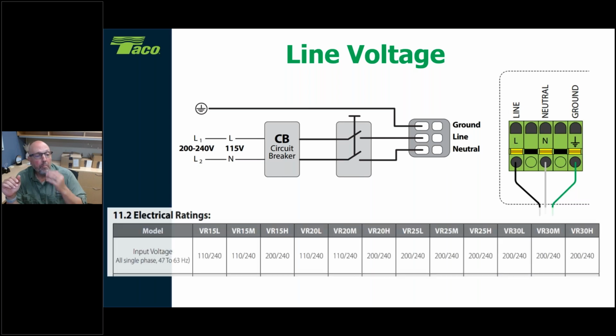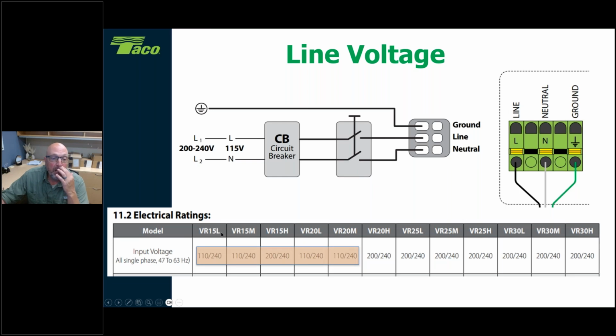Now, when we take a look at the models here, this is where I've seen some confusion, and a couple of phone calls have come in saying, hey man, my circulator's not running, it's really slow. I got VR15s on here, and they went with the VR15H. So you'll see here the VR15 through 20M. Say, oh, look at that, these are all 110s and everything else is 200 to 240. However, the VR15H is a 200 to 240 circulator, not a 110 voltage.